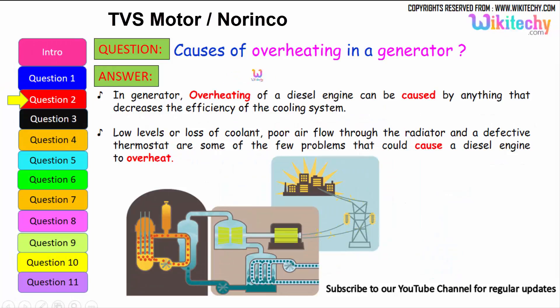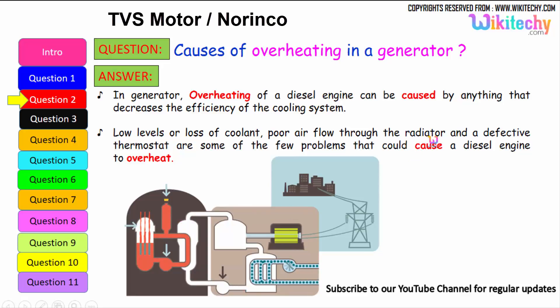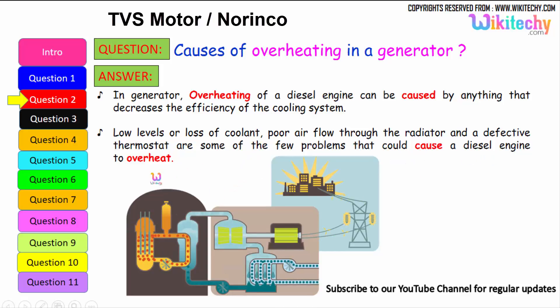Let us move on to the next question: causes of overheating in a generator. Overheating of a diesel engine can be caused by anything that decreases the efficiency of the cooling system — such as loss of coolant or low coolant levels, poor airflow through the radiators, and a defective thermostat.